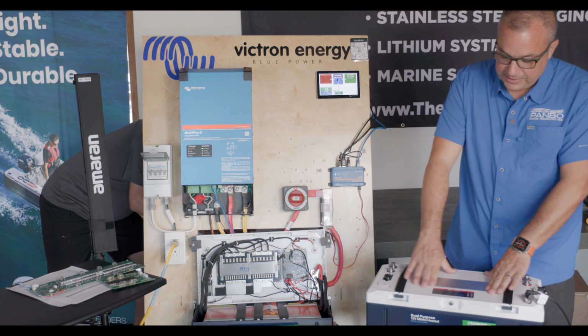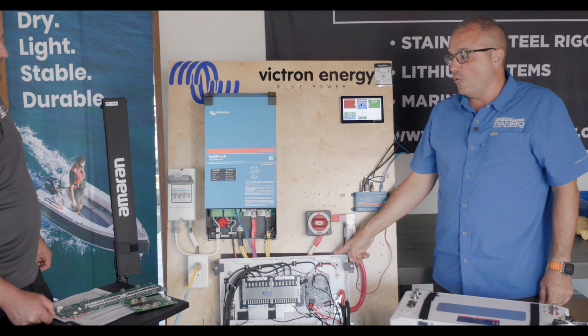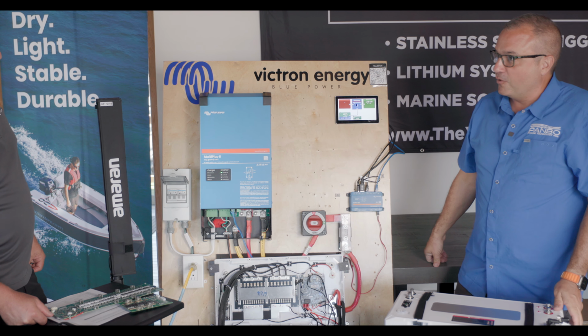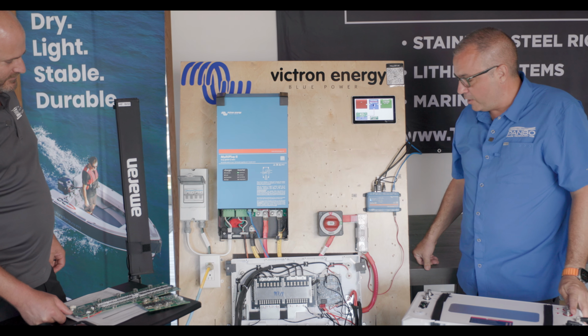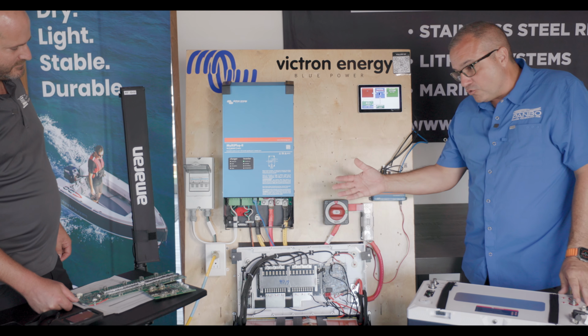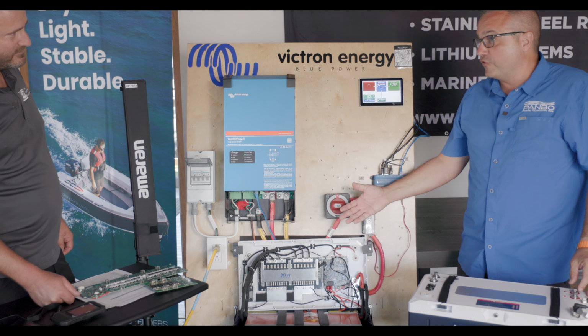It's another reason why, when we talk about appropriate installation locations for lithium batteries, if the ambient temp is too high, you're going to sacrifice the battery's ability to cool itself because a heatsink isn't as effective in the same ambient temp. It's at 104 degrees, so it's 30 degrees above ambient, and it's effectively shedding heat from the battery. To be fair, this battery was never meant to produce 180 amps with the case open and heat not rising into the heatsink, so we're kind of compromising it that way.